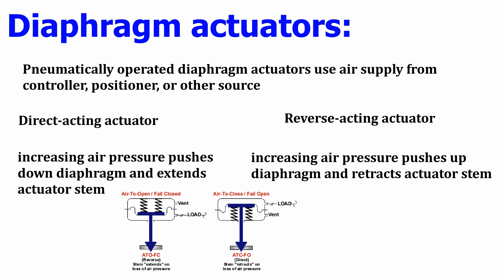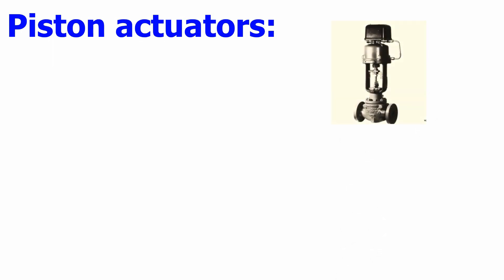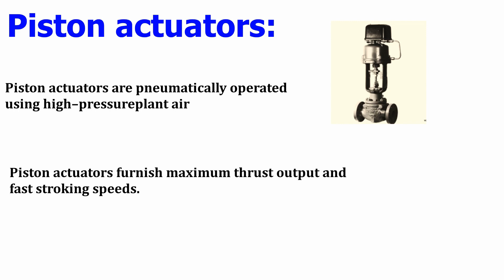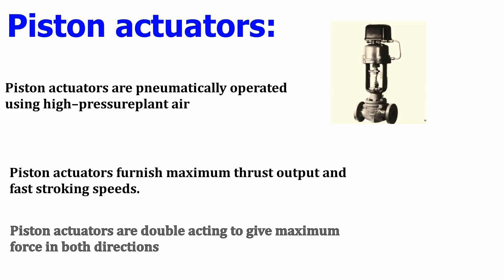Next, we look at piston type actuators. Piston type actuators are pneumatically operated but they use high pressure instrument or plant air — sometimes more than 8 bar or up to 150 psig. Piston actuators provide maximum thrust output and have a unique feature: fast stroking speed, making them suitable where immediate action is needed. They are double acting, providing maximum force in both directions, and can be used for both direct and reverse acting.